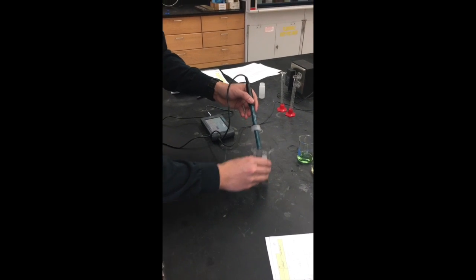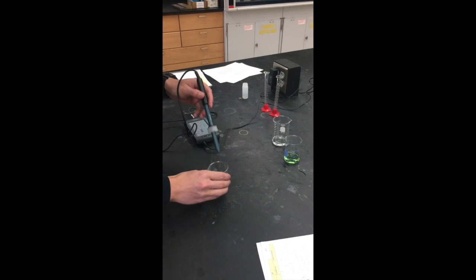Rinse the probe off again and put it into the known pH 4 buffer solution, and enter pH 4 into the meter, and tap Keep.